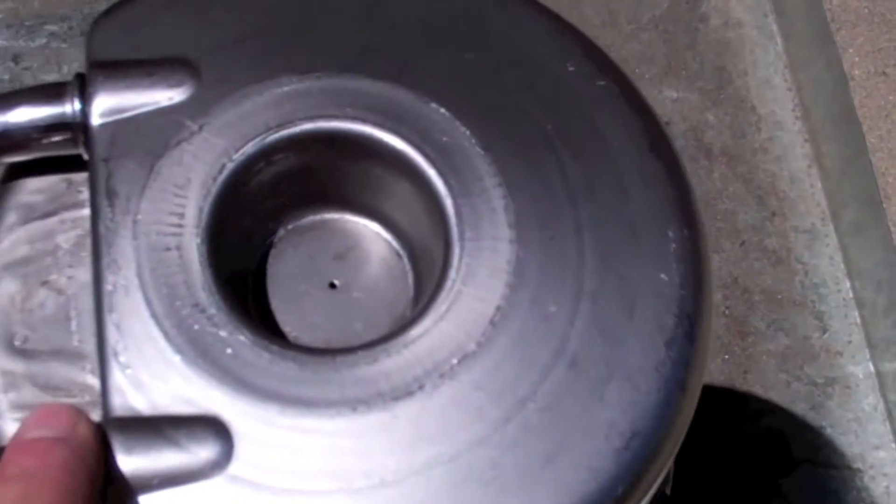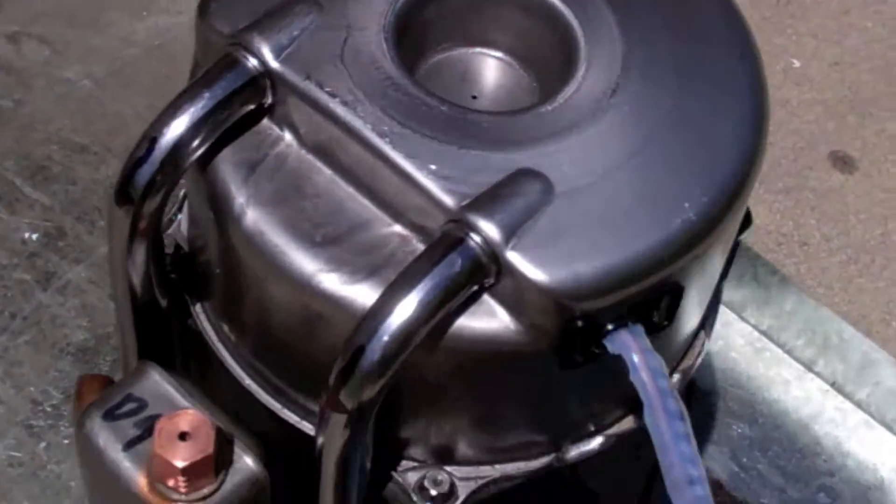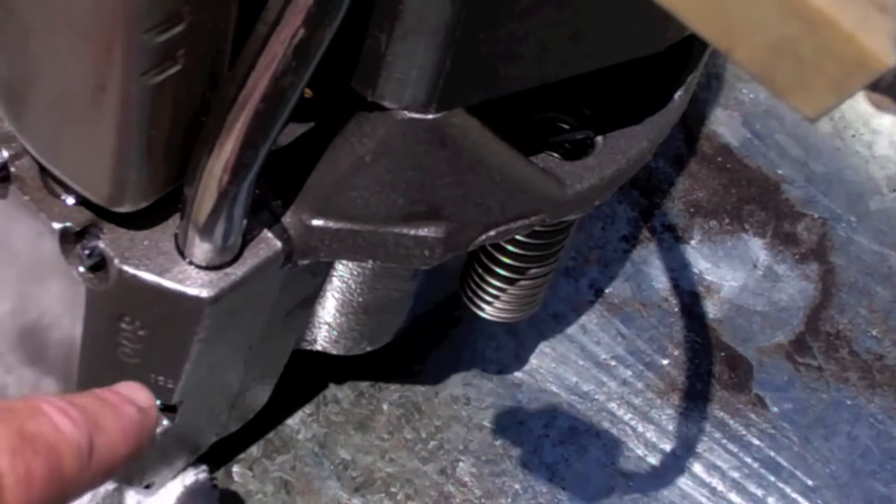So the gas comes in through this hole. Some of it drops, it cools the windings on the bottom, and then it comes down these tubes here. This is your suction coming down, and then your valves are going to be down in this area right here.